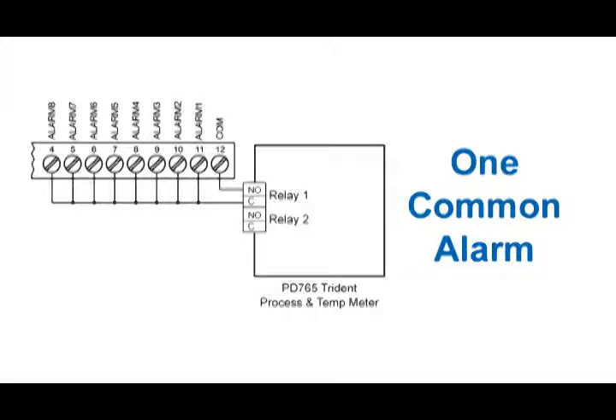So if let's just say the Minimux is on channel six and alarm number one is above the set point, alarm number one will not go into alarm because the Minimux is not looking at that channel. It's only looking at channel six. When it got around to alarm number one, then if it was still above the alarm condition, the alarm would occur. So it's important to realize how the alarms work.